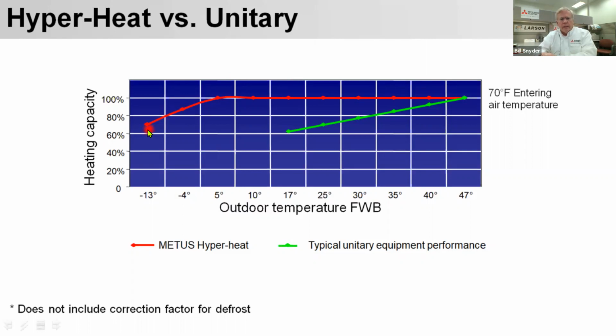At minus 13, it's going to drop down to 70 to 80%, 75%, right around their capacity. So this same 3-ton heat pump, which is giving us 45,000 BTUs of heat at 47 degrees, is going to give us about 34,000 BTUs at minus 13. So we're getting 34,000 at minus 13. Our competition is getting 36,000 here, and right here at 17, they're going to get about 21,600. Depends on the equipment, the rating, but that's generally how it works.